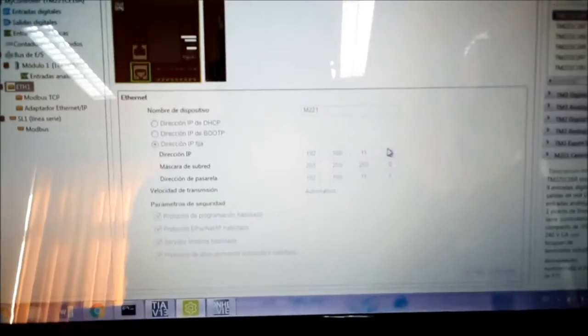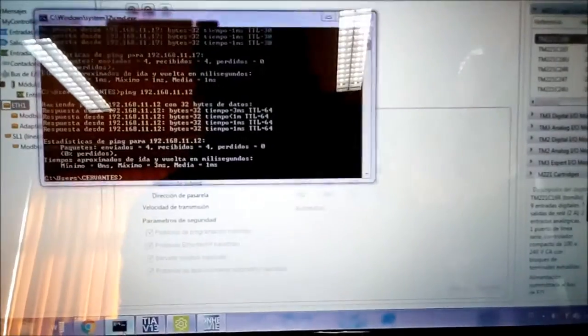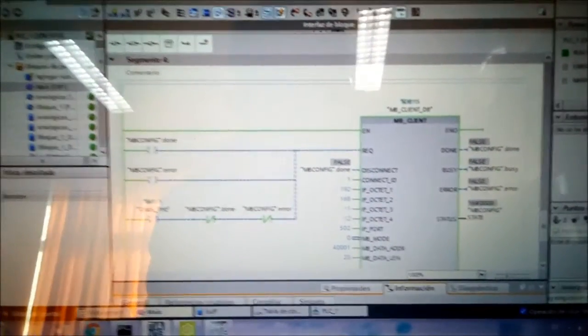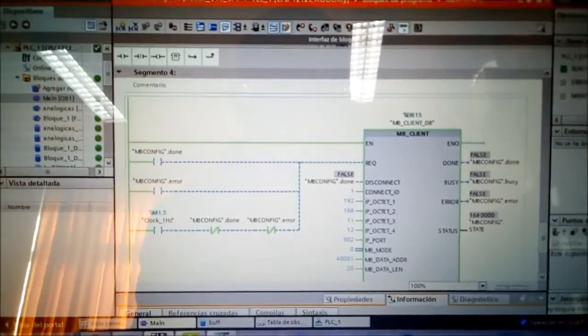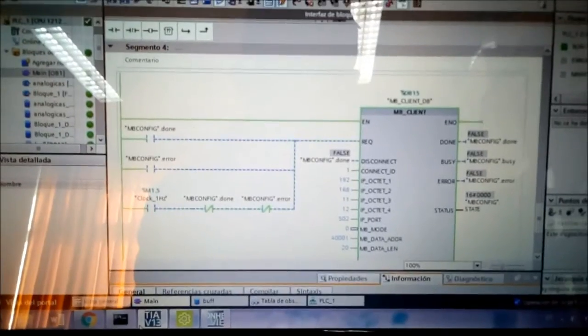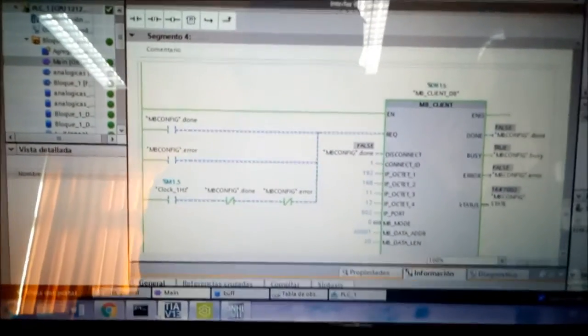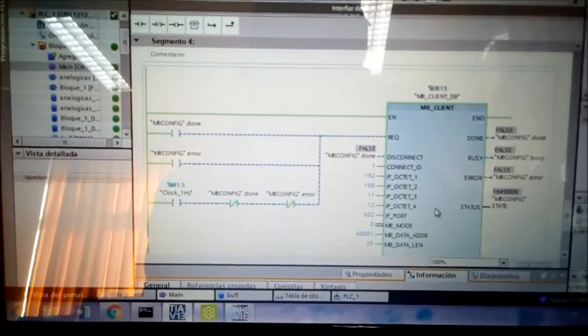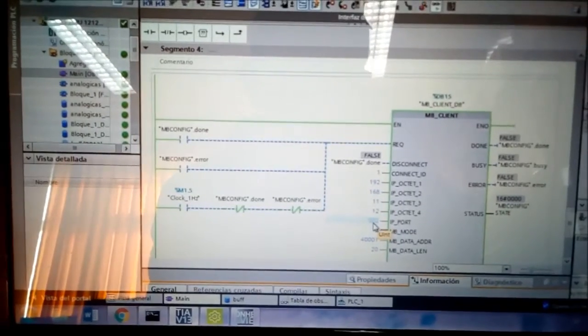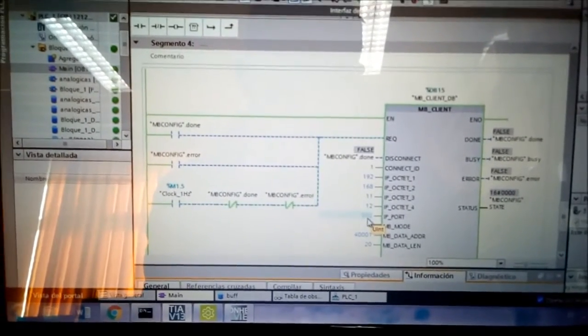It's got to be the same one as our PLC. As you can see here, I'm online. And this one is 12, too. So I'm using this block to read and write values from the Schneider PLC to the S7-1200. Next, we have the IP port. It's the predefined one, 502.